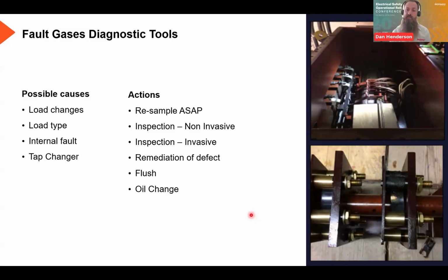And then obviously invasive. So we've got a picture there of the transformer that's being partially drained down, then the lid removed, to try and do an inspection of what's there, to identify where that issue is, in order to identify the defect and then remedy that defect. Again, linking back to the first one, we've got to make sure that the conditions are good and that we control the transfer of oil, so that we don't put any pollutants into that transformer, any debris, any water content, things like that. So we need to make sure we do that right.